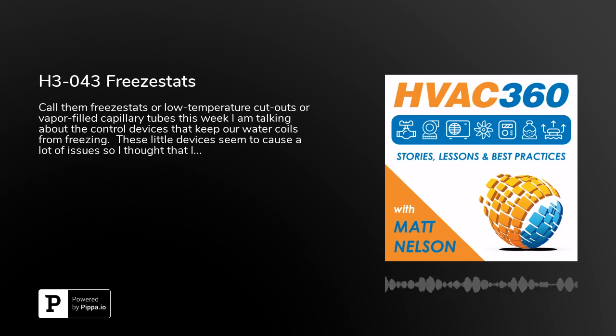So you want to be able to cover basically the whole coil, and the tube wants to be a foot apart, because the foot of coverage says, okay, 6 inches down, 6 inches above, that covers the coil for that square foot. So between the different rows, you're going to have about a foot of spacing, and you want to end your last row of the sensing element 6 inches above the bottom of the coil.